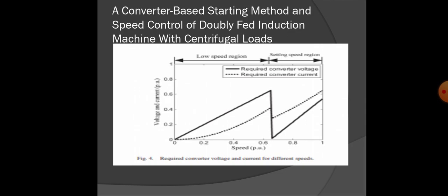The voltage amplitude, angle and frequency are adjusted. Next, when the voltage amplitude and angle errors enter the setting tolerance, KM1 is closed and the machine rotor side is connected to the grid, with vector control for the double fed induction machine. The speed reference is compared to the speed difference and the normal rated speed. KM2 closes and KM1 is open. Constant voltage and frequency is controlled, and this is the required converter voltage and current at different speeds.